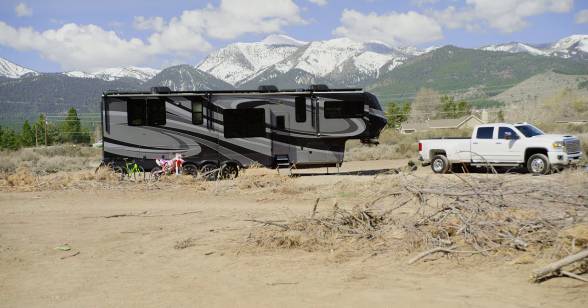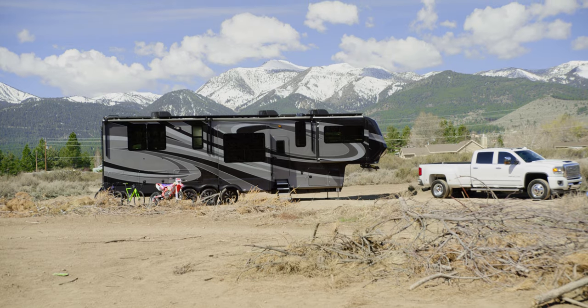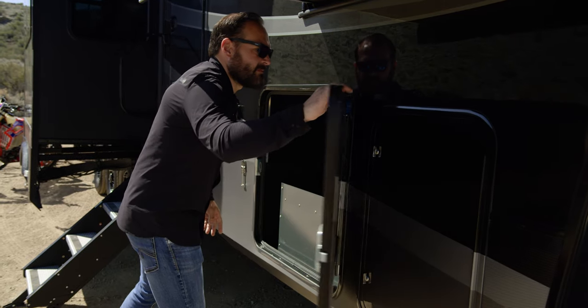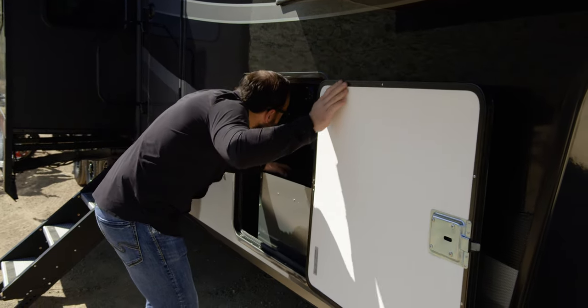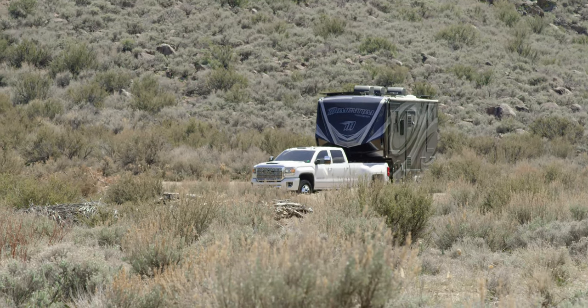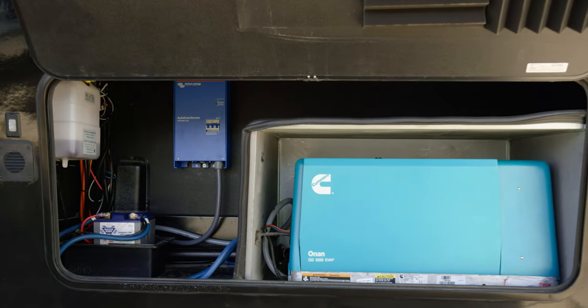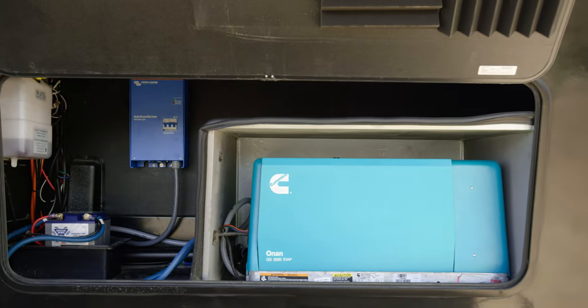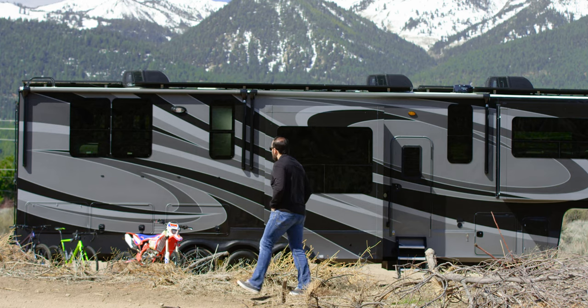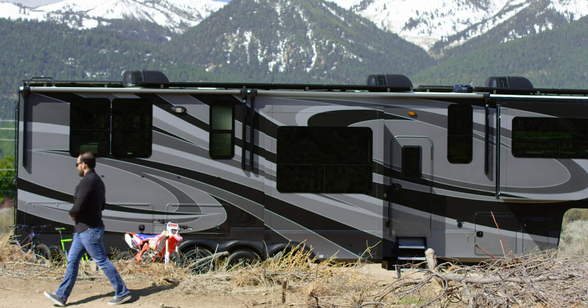When I designed the system, I needed it to be as foolproof as possible — I couldn't have one part of the system fail without a backup for it. Just this last winter down in Southern California, there were days on end where it was completely overcast and raining, with no solar coming in. If I get to five or six days without solar, I start really draining my battery bank, which is where the emergency backup — my 5,500-watt Onan with the auto transformer — allowed me to continue staying off-grid. It's a failsafe, and I have to have failsafes because my system has to run no matter what.